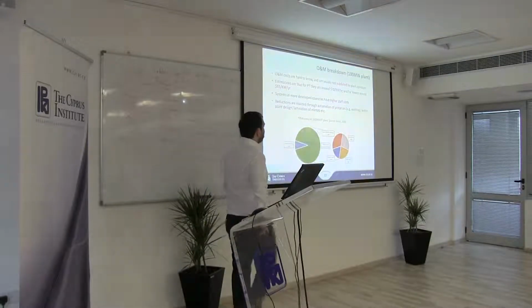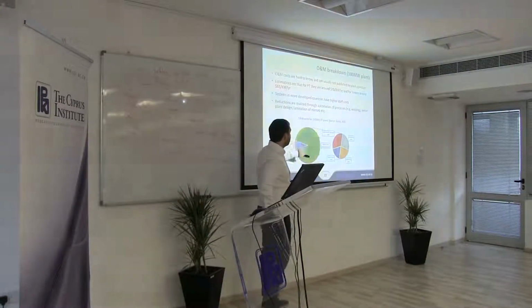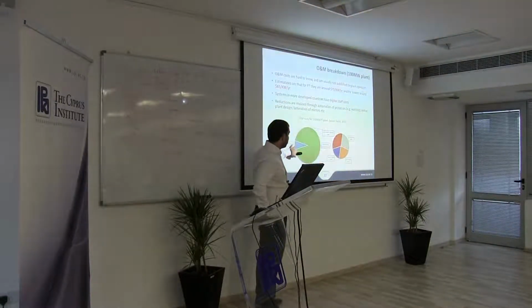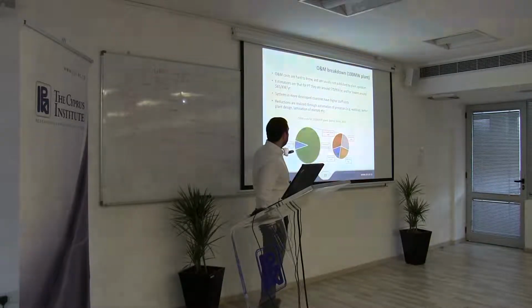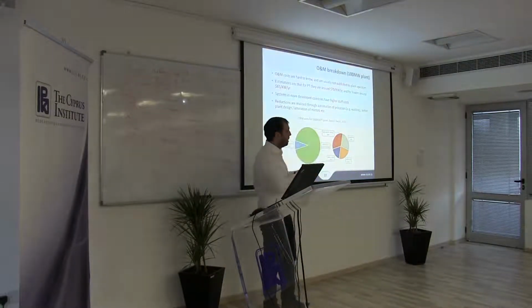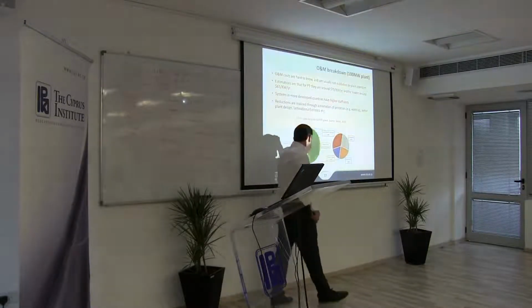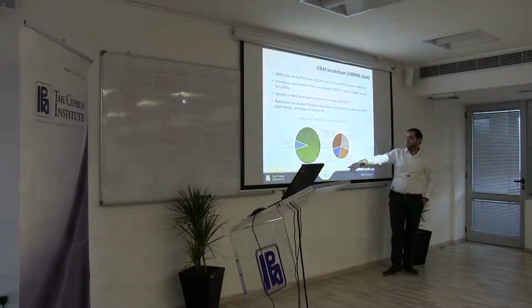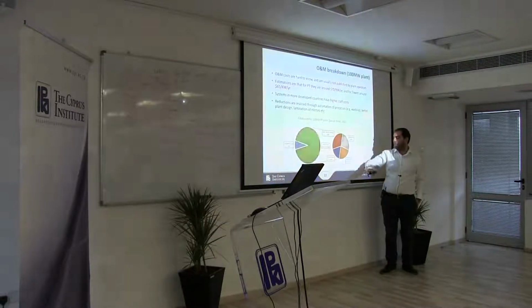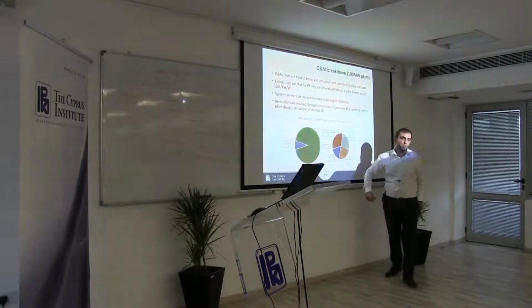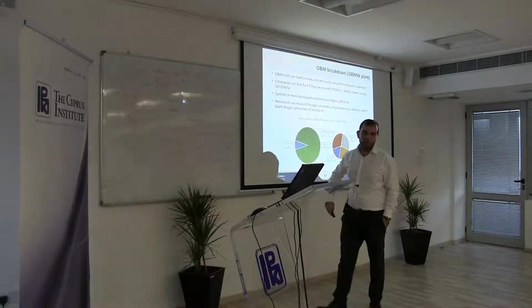Here we have an example of a 100 megawatt parabolic trough plant, where you can see that the variable operation and maintenance cost is only 8%, whereas the fixed operation and maintenance cost is 92% of the total operation and maintenance cost of the plant. And this is broken down mainly into maintenance of the solar field and storage as a first factor, then insurance and staff costs, and to a lesser degree maintenance of the power block.